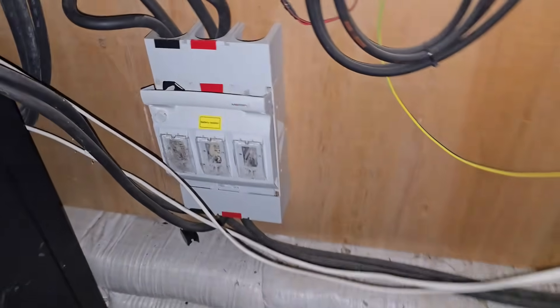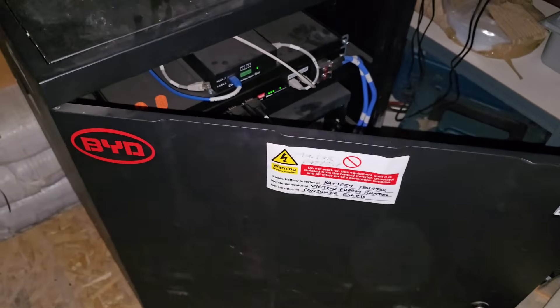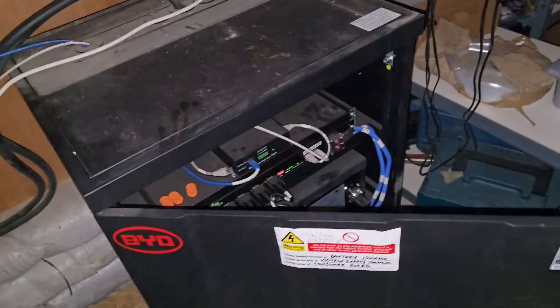There's a little on/off switch just here. These are an absolute nightmare to get back on if you do — when that fuse went it was an absolute nightmare to get the main system back on, because you had to cycle these batteries in sequence to give that computer system enough power and time to boot up before it recognized the batteries again. Hoping the new ones don't need that, because they've got a bit more technology. These have some sort of self-regulating thing where they just instantly turn back off if they don't recognize being part of a system — I'm guessing it's a safety feature.